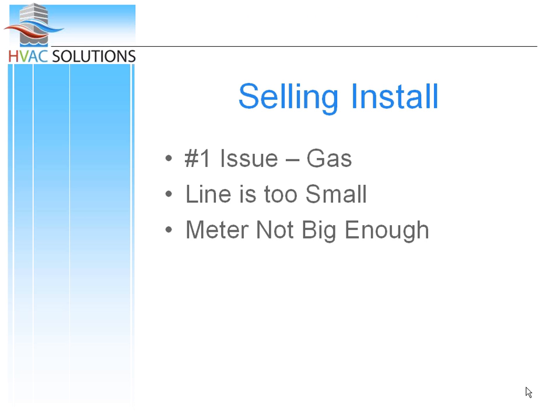On the install, I get asked all the time: what is the number one issue when installing generators? So I called up Generac and asked, when your people are on the phone, what is the number one issue that you run into? And hands down, they all said the gas. From the gas, it broke down into a handful of different issues, but generally speaking, the gas line was too small. So if anybody has issues sizing these things or questions, please call me. I could tell you some war stories where I've seen a half-inch gas line after the furnace piped out to the generator, and they couldn't figure out why it didn't work.